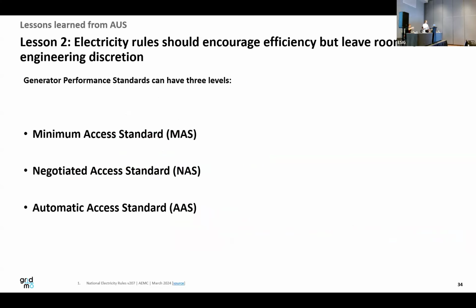Lesson 2, again around standards. Putting standards together is a great process of making this more efficient and trying to avoid every generating system being bespoke. The way our generating performance standards are defined is by what set of undervoltages you have to ride through to not trip.